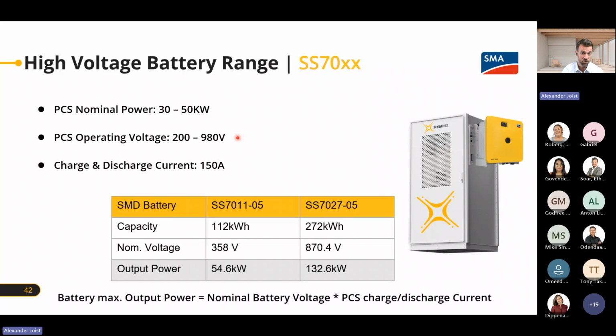Same thing, the quick calculation we did earlier with the Sunny Island. Sunny Island has a charge and discharge current of 150 amps, which is a little bit higher than what we saw earlier from the GoodWe, for instance. So now you can choose a smaller battery to actually deliver 54.6 kilowatt. So now with this 150 amps, you can install a 112 kilowatt hour battery and can use the full capacity of the Sunny Island, right? So it's the same calculation that we had earlier in this slide as well. So that's why the SS7011 will be enough for one Sunny Island to give the full output power of 50 kilowatt, right? So just be aware of that. So high charge and discharge currents up to 150 amps are very good for these smaller 50, 70, 80, 100 kilowatt hybrid inverters.